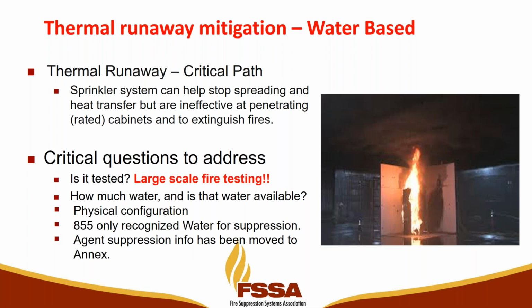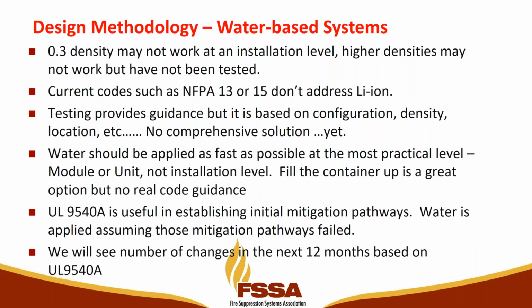What's your physical configuration? NFPA 855 only recognizes sprinklers as a viable option for suppression right now, but there is a TIA going through that's actually going to limit that. Only for small systems are you allowed to use water. Anything above that, you have to do some large-scale testing to figure out whether it's going to work. I mentioned the 0.3 density. It was interesting, from what FM did.